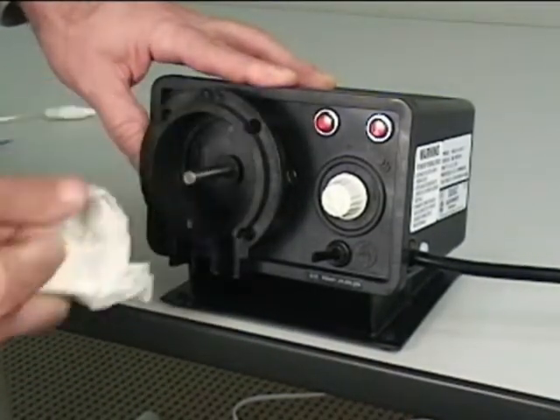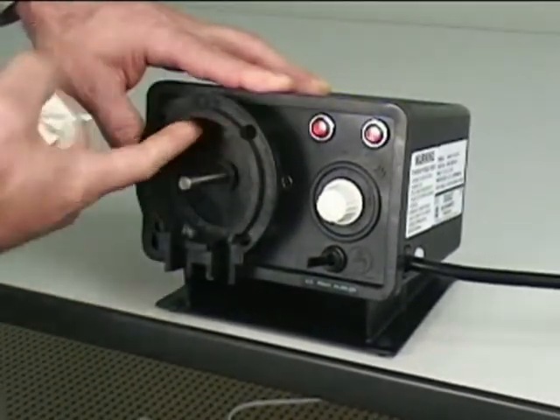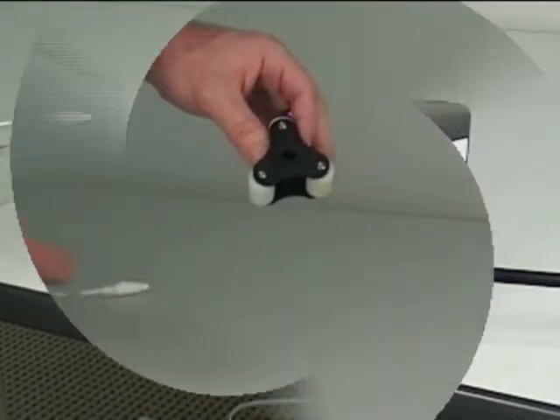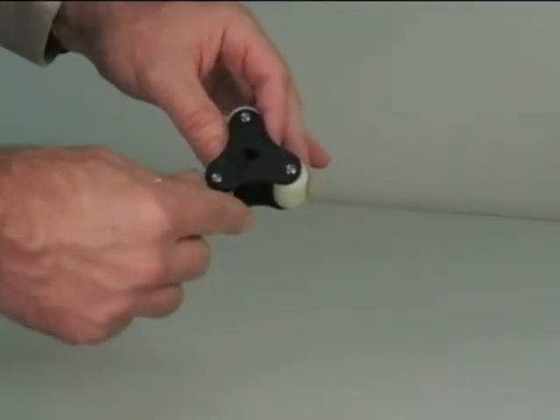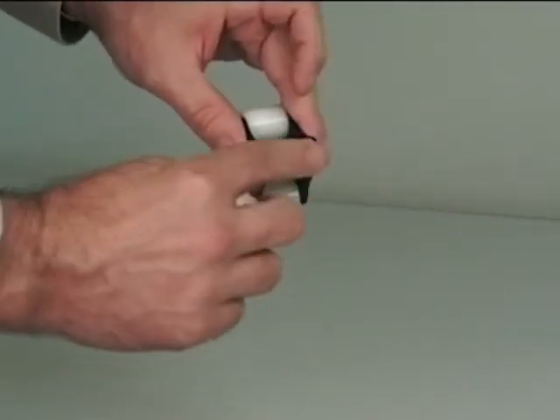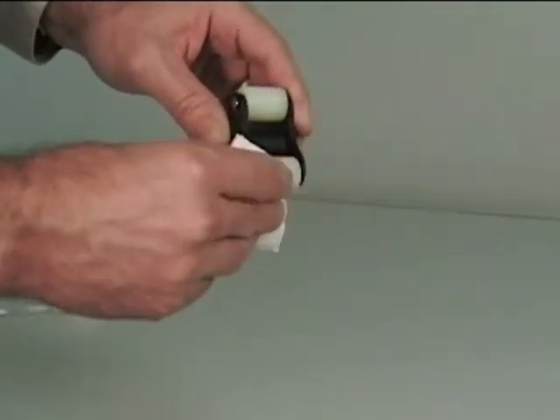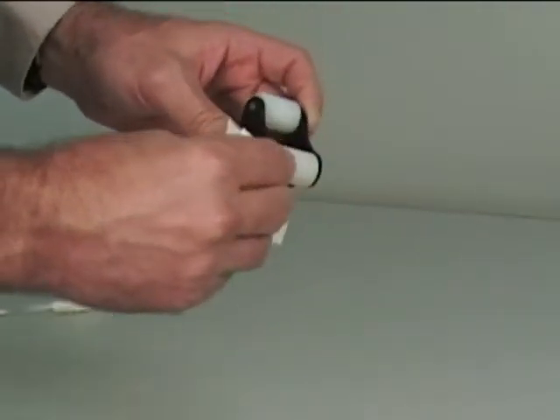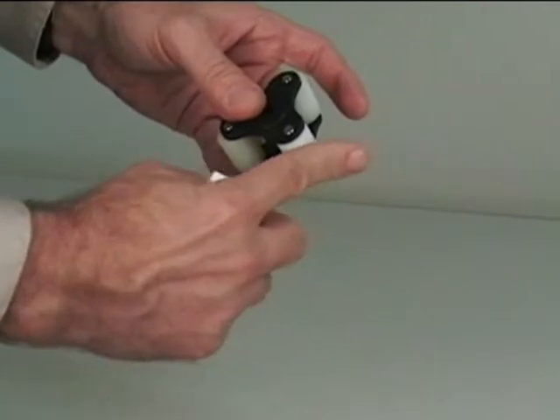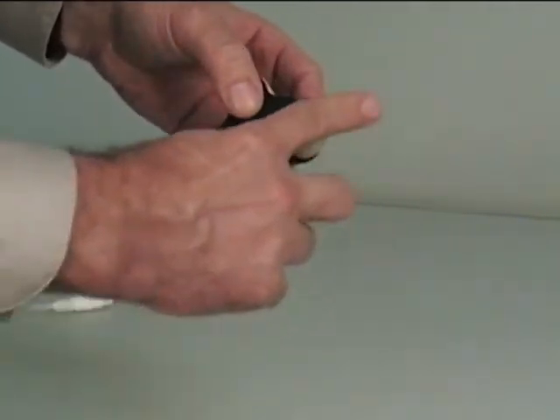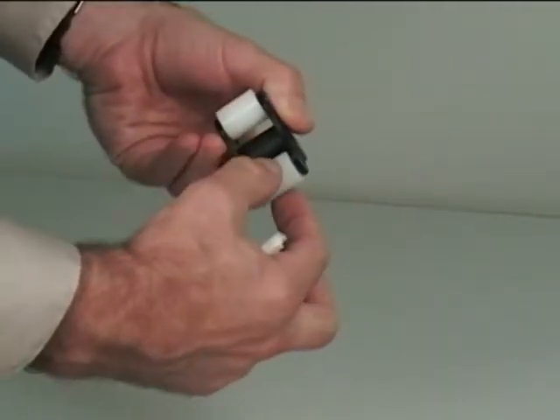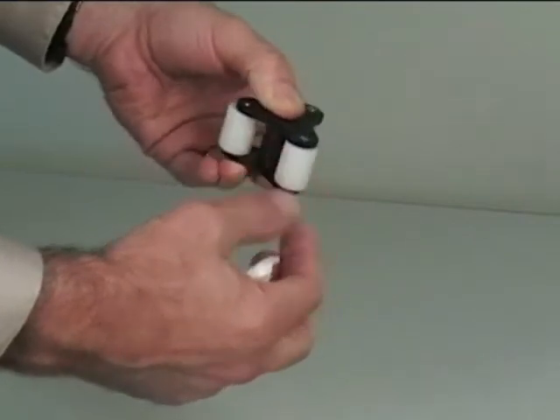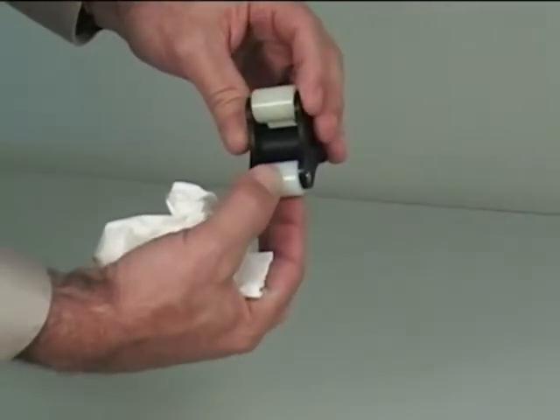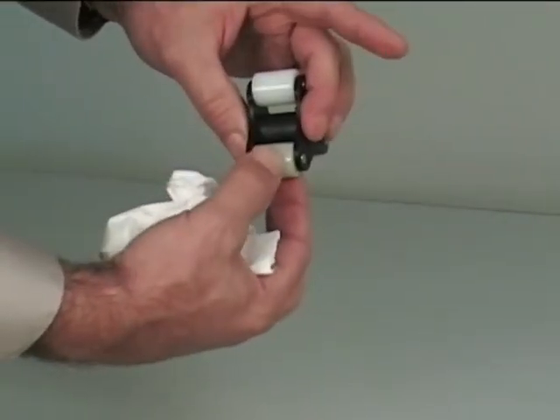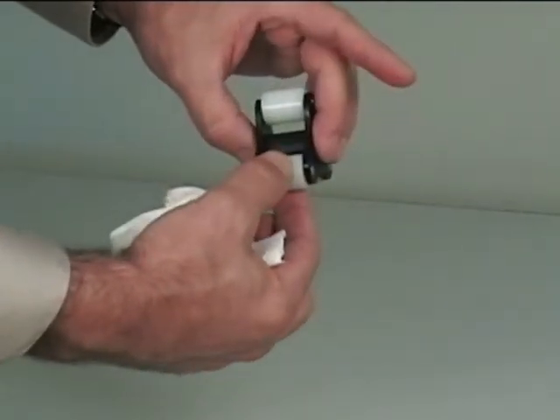Be sure that power to the pump has been turned off. If the roller assembly does not easily slide off of the motor shaft, clean the end of the motor shaft with light sandpaper and a small amount of oil. If required, a screwdriver can be used to gently pry the roller assembly off of the motor shaft. Thoroughly clean the pump head and the motor shaft. Any dirt or debris left in the pump head will increase friction in the pump tube and reduce the life of the tube. Thoroughly clean the rollers.